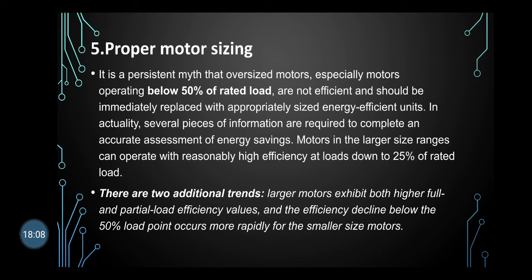Actually, several pieces of information are required to complete an accurate assessment of energy saving. Motors in the larger size ranges can operate with reasonably high efficiency at loads down to 25% of the rated load. There are two additional trends: larger motors exhibit both higher full and part-load efficiency values, and efficiency decline below the 50% load point occurs more rapidly for the smaller size motors.